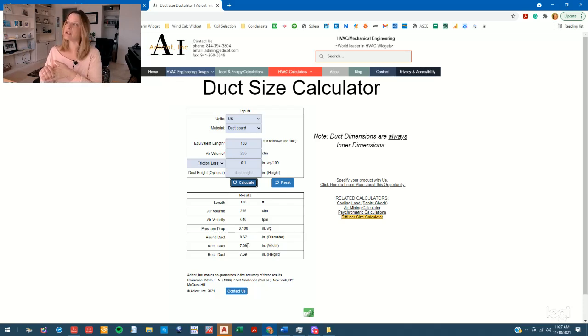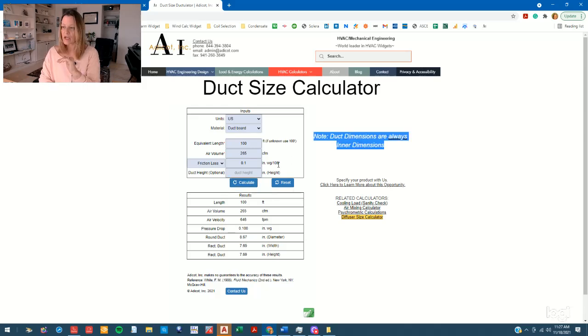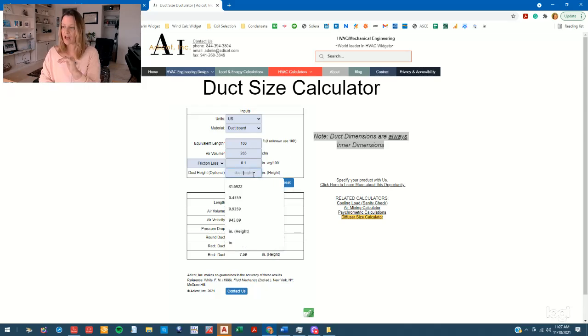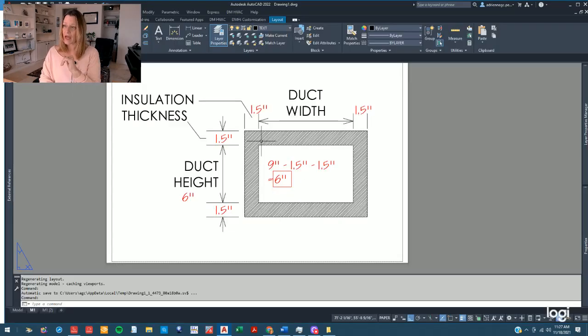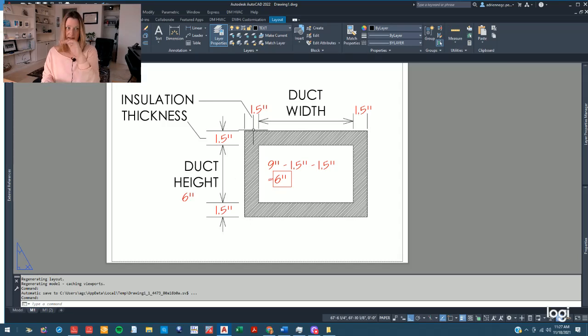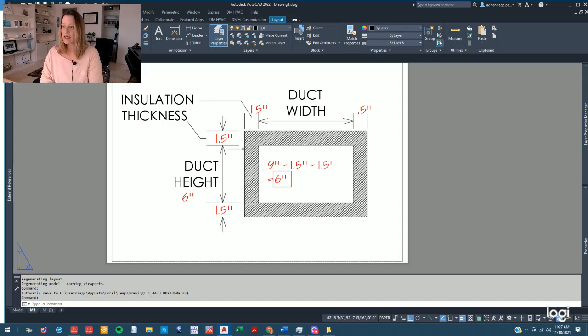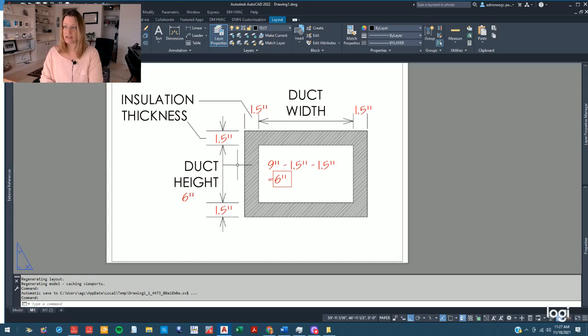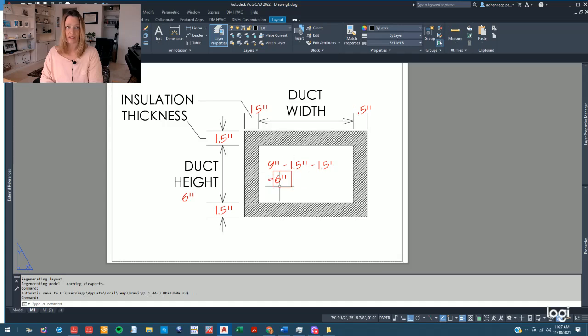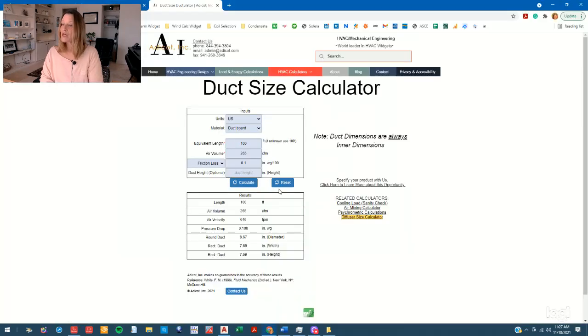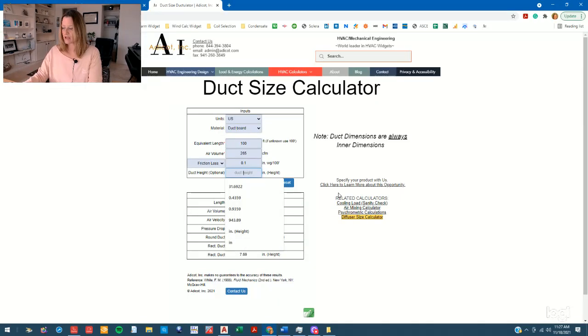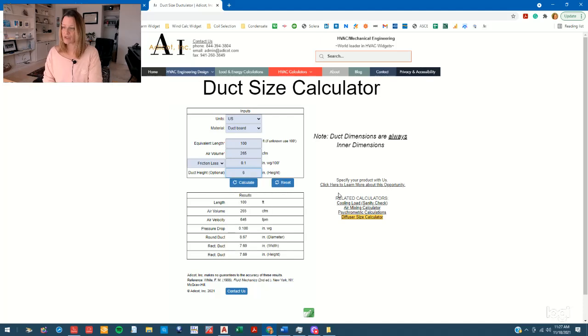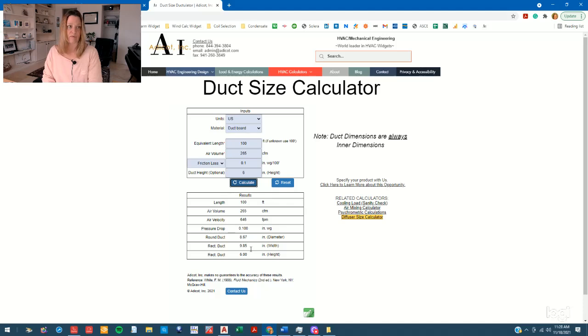We're probably going to assume that it's going to be a rectangular duct. So let's say we have a constraint where the outer dimension height of the duct is a maximum of 9 inches, and we have 1.5 inch thick insulation on the top and the bottom, which means our inner dimension is a maximum of 6 inches. So our maximum duct height needs to constrain to 6 inches, and then we can calculate that again. So now we know that our rectangular duct is going to be a 6 by 10 inch duct.